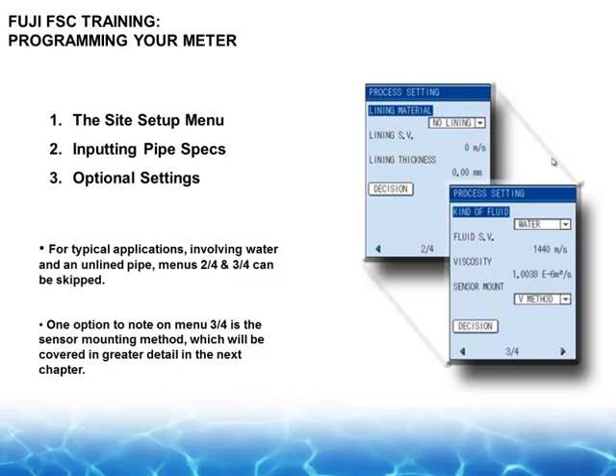Mathematically, it worked fabulous, but you couldn't deter from that. You had to put the different sound speeds in for everything. Not so anymore. Now it has an auto gain function that basically allows you to digress plus or minus 10% of the sound speed without any substantial effect on the performance of the meter. And if you look at the diagnostic screen, you'll note that even if you put in water, it'll change the sound speed to optimize its performance.